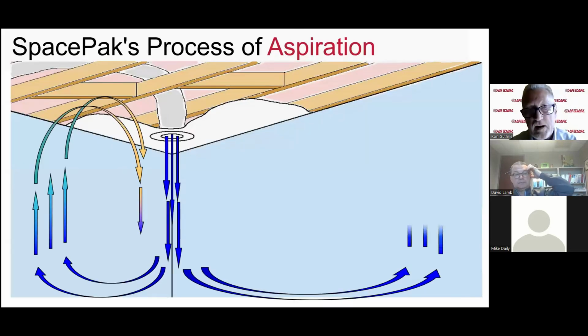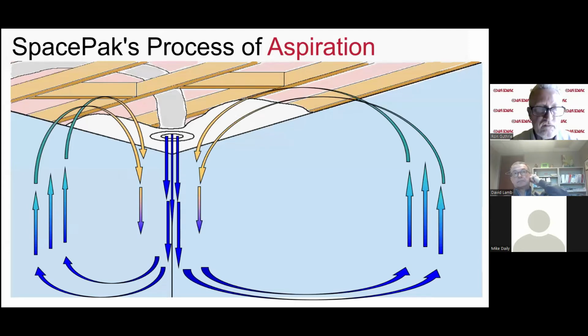But what we use to move the air in SpacePak small duct high velocity systems is a process known as aspiration. All right, so aspiration means sucking. If you're watching your favorite medical show and the doctor tells the operating team to aspirate, that means they suck out all the stuff. Okay, a little bit gross, but just wanted to give you another example of the word aspiration or aspirate. When we do this, we have a slight negative pressure, right at the outlet of the 2-inch tube at our outlet. That negative pressure pulls in the room air and feeds it into that high velocity stream that's coming out of the nozzle. So we use a different process to move air around the room.